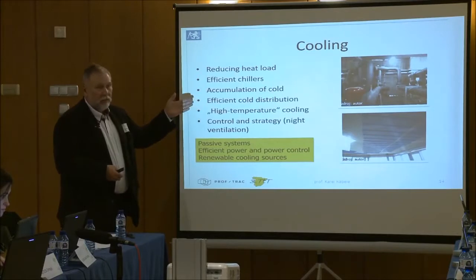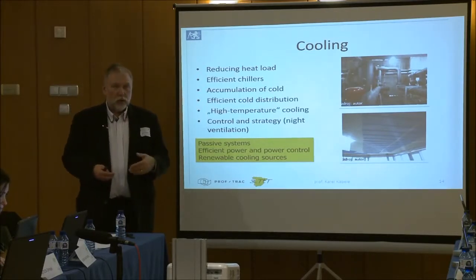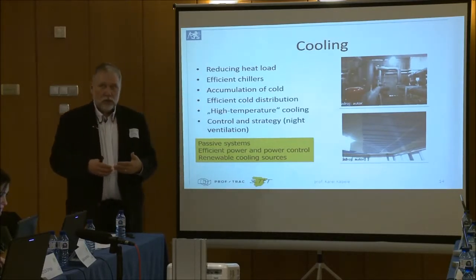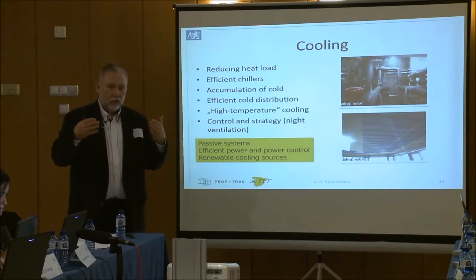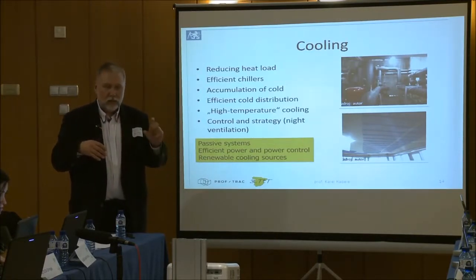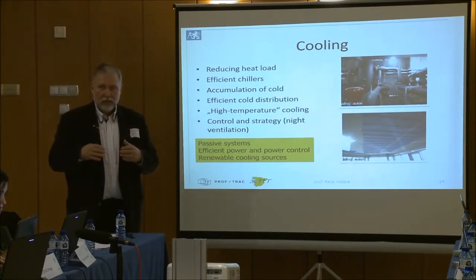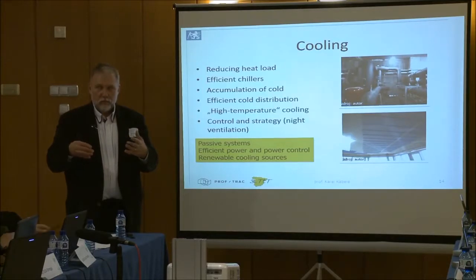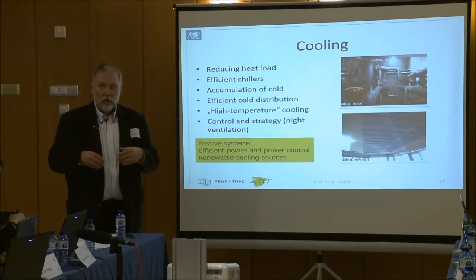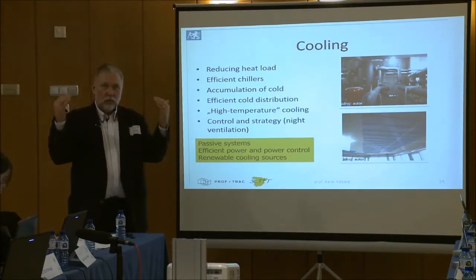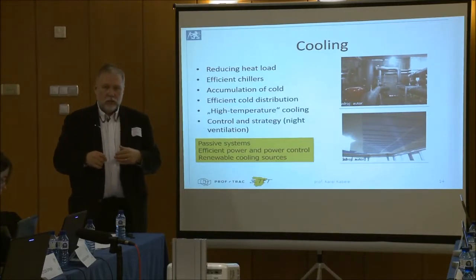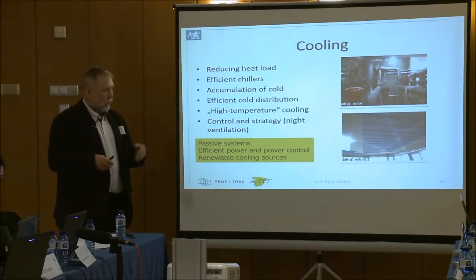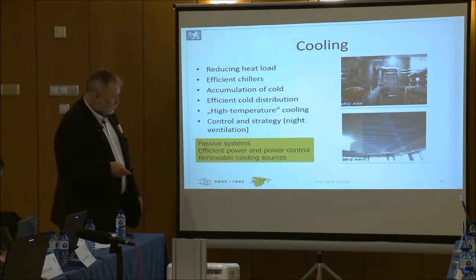Big challenge is high temperature cooling. That means using systems with higher temperature cooling water - not 8 to 12, but let's say 16 to 20 or something like this, which are much more efficient. We don't lose so much. But on the other side, we need some large exchange surfaces, like the floor and so on.